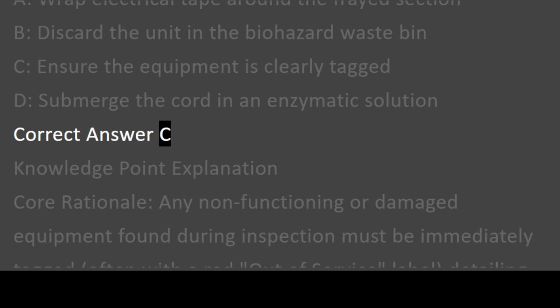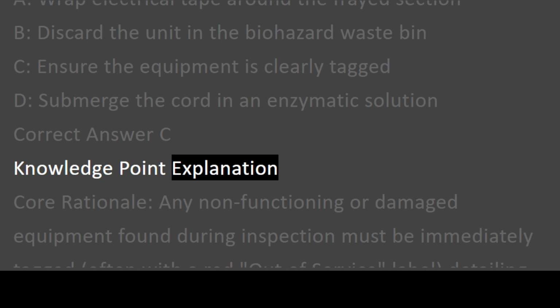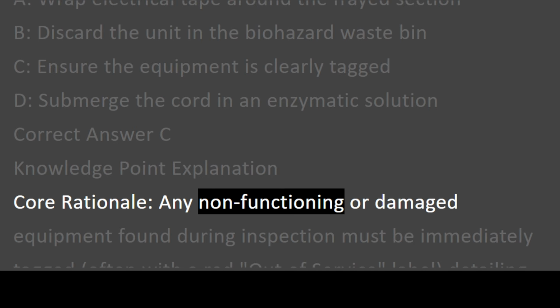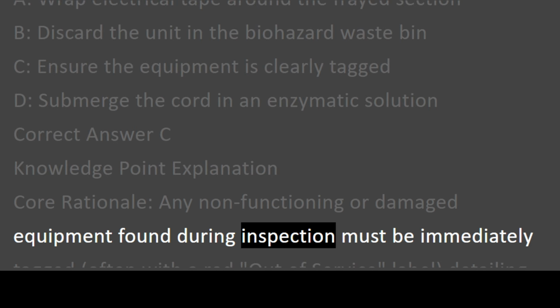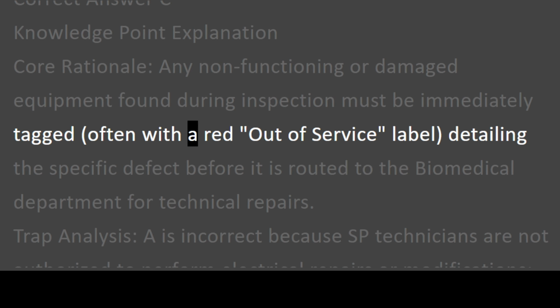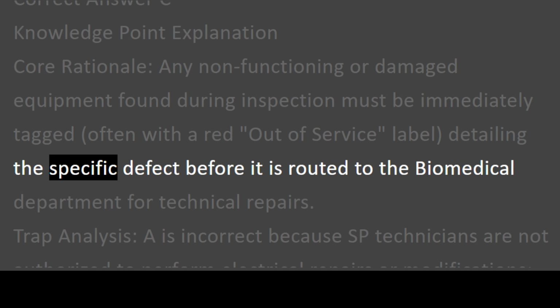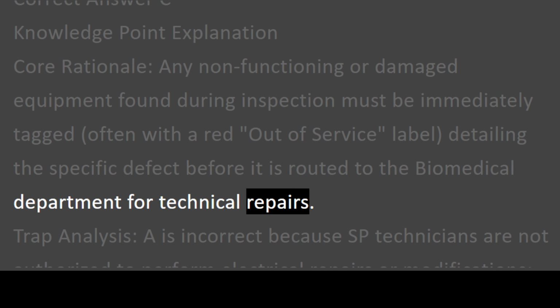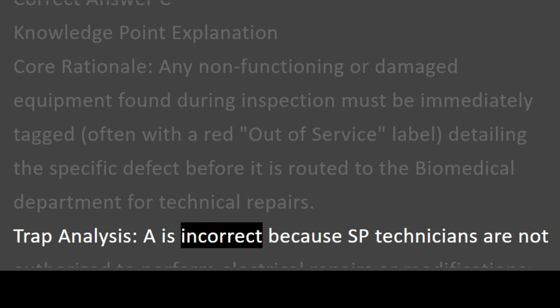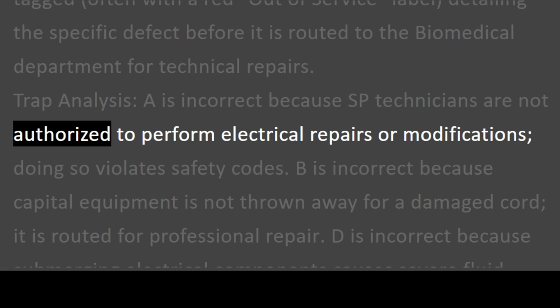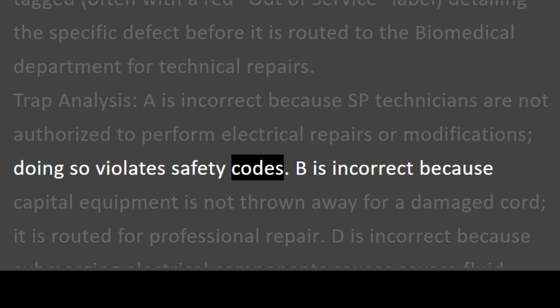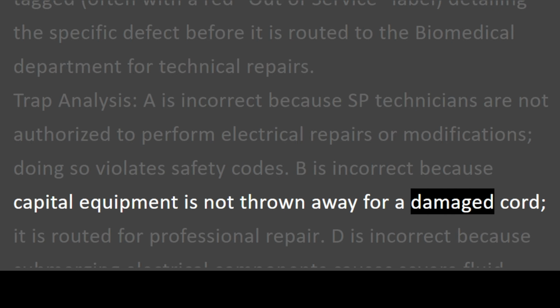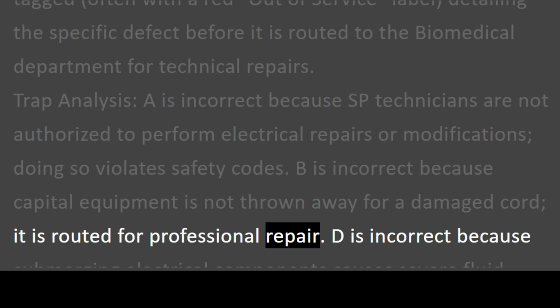Correct answer C. Knowledge point explanation. Core rationale: any non-functioning or damaged equipment found during inspection must be immediately tagged, often with a red out-of-service label, detailing the specific defect before it is routed to the biomedical department for technical repairs. Trap analysis: A is incorrect because SP technicians are not authorized to perform electrical repairs or modifications. Doing so violates safety codes. B is incorrect because capital equipment is not thrown away for a damaged cord, it is routed for professional repair.